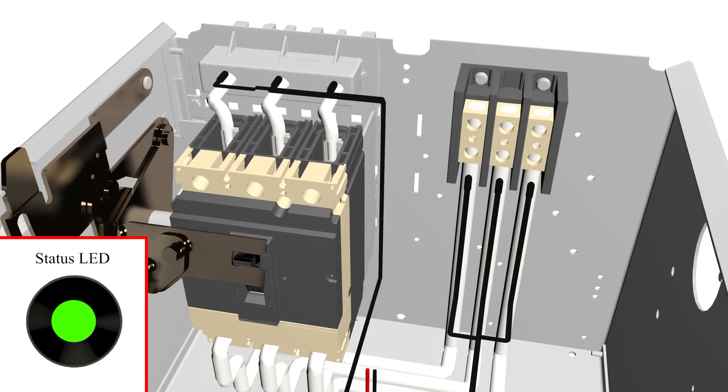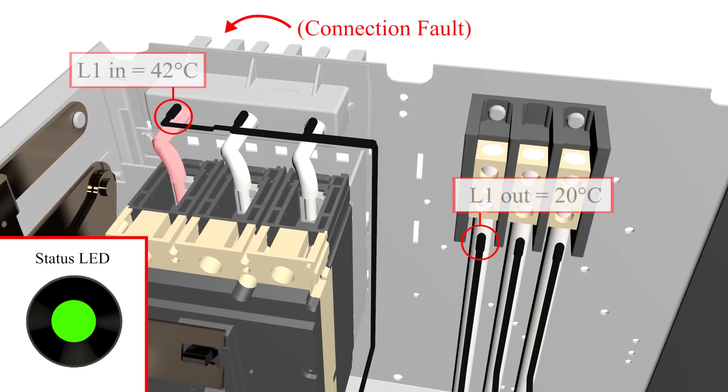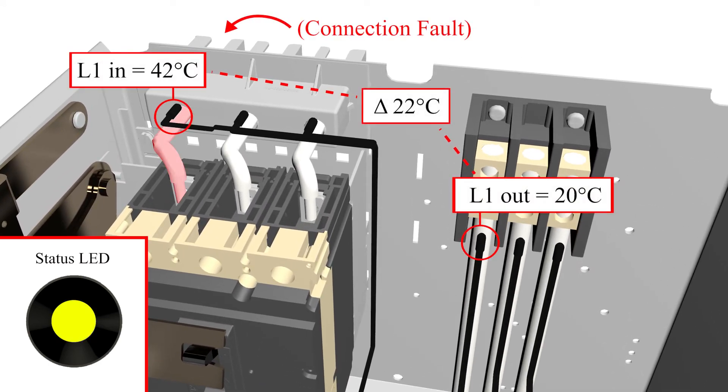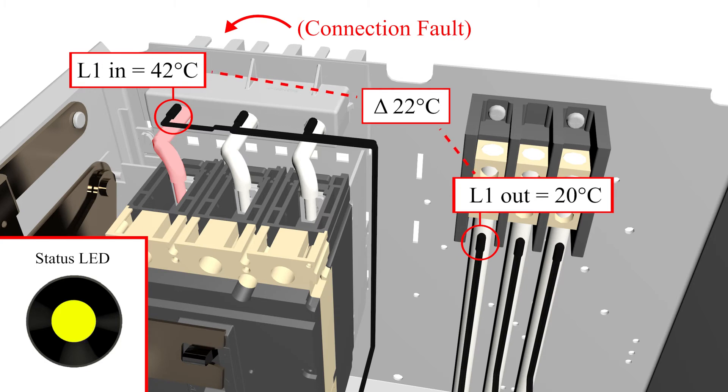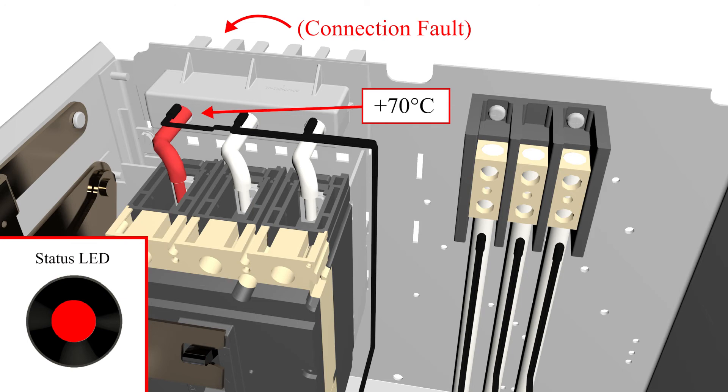For a failing termination, there are two alarms generated. First is the warning level alarm, for which the status LED will flash yellow. Should the temperature continue to increase, then a high alarm is triggered and the status LED will flash red.